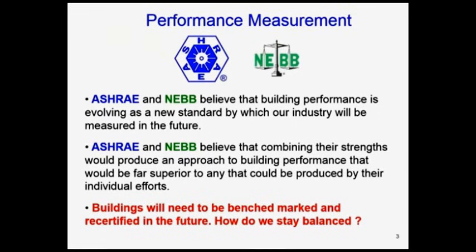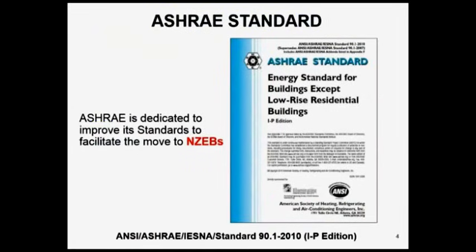So let's talk a little more about where we're going, what's happening, and the future of balance. Basically, ASHRAE is working with NEBB. We're trying to get the balancing procedure started. Now, what does this have to do with ASHRAE? It's very simple. These ASHRAE energy codes, and particularly Energy Standard 90.1, are a long-term attempt by ASHRAE to drive us to net zero energy buildings. That's the whole concept. And what's really gotten active has been ASHRAE 90.1 2010.